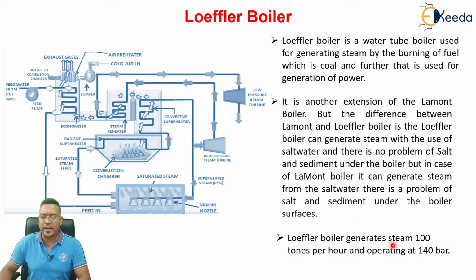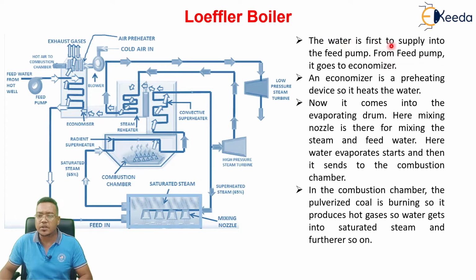Loeffler boiler generates steam at 140 bar and a quantity of 100 TPH. The water is first supplied to the feed pump. From the feed pump it goes to the economizer. You see here the water is going from the feed pump to the economizer. And after the economizer, this water goes into the mixing chamber.